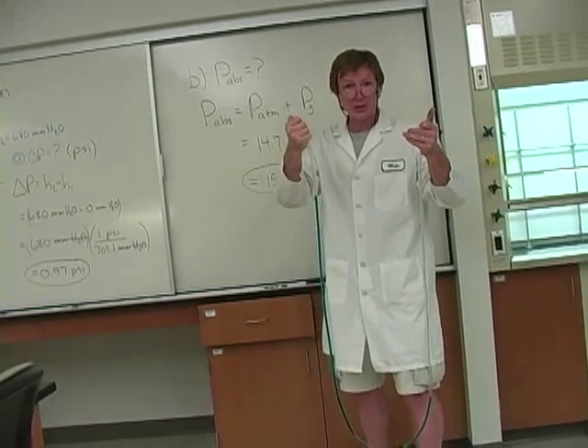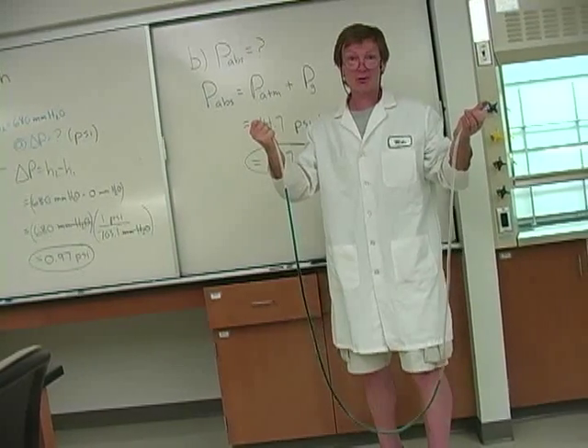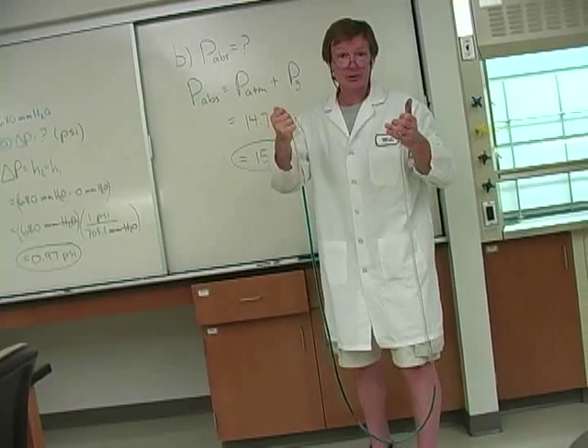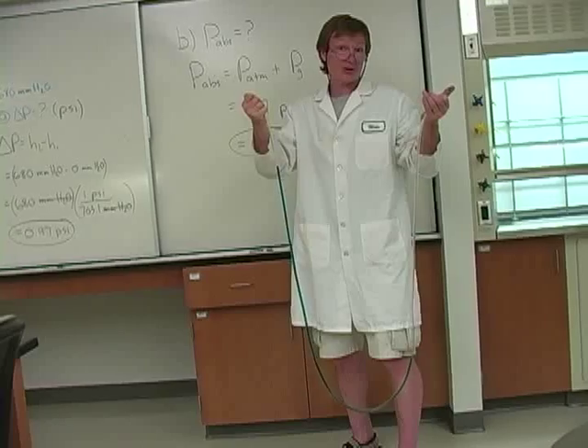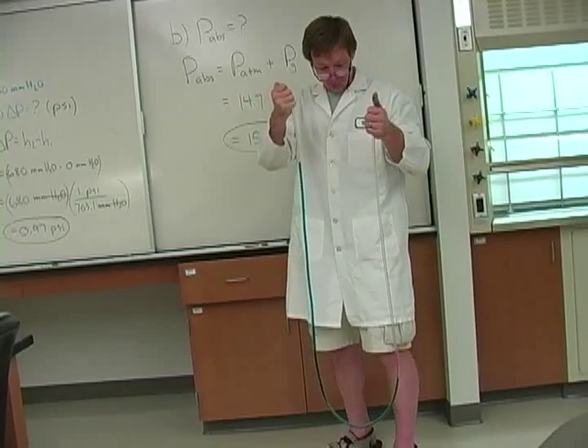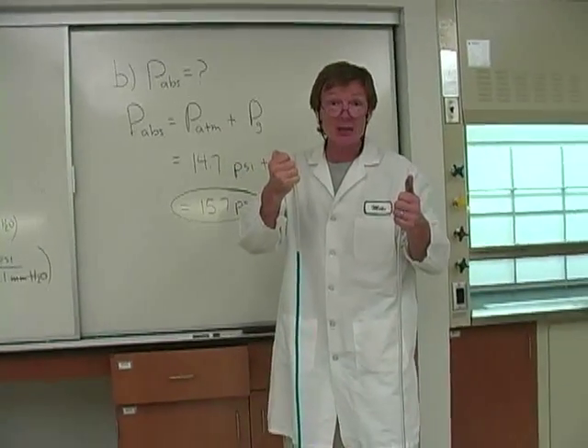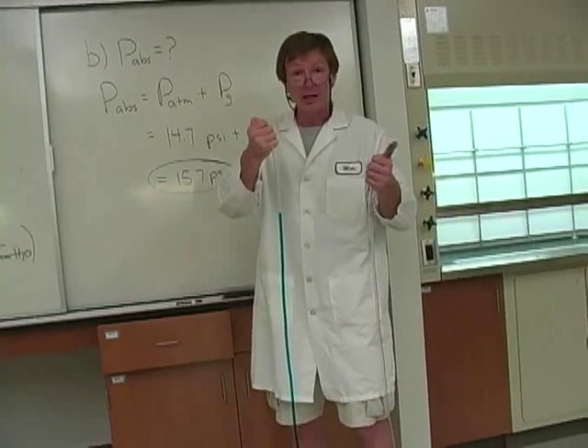Well, now I'm going to have negative pressure, because the atmospheric side is pushing harder than the test side. So negative pressure. Now, I can't have negative absolute pressure, right? If you take all the molecules out of a room, that's it. That's all you can do. But I can have negative gauge pressure. How low can the negative gauge pressure go? It can go down to minus 14.7 PSI. Right here, it looks like I pulled out, it looks like I've got about negative 680 millimeters of water this time. About the same height, just on the other side.